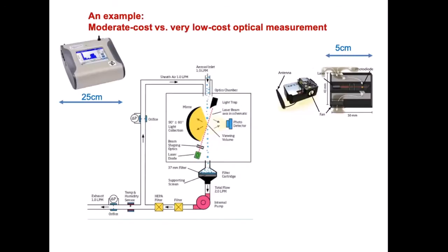Now let's look at moderate cost versus very low cost optical instruments. Here is the low-cost instrument in its simplicity and size, about 5 centimeters. This is a moderate, small optical particle spectrometer—it counts particles and measures particle size. You see here some size distribution, and you can see that the internal design of the system is quite complex.